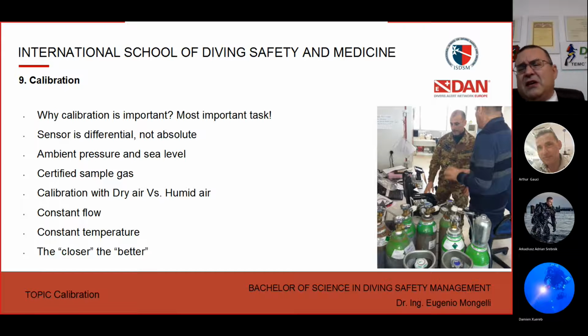Typically it's Air Liquide, Sapio, or SIAD, the typical gas suppliers, and they provide us this mix that is certified, meaning it comes with a certificate. They use a gas chromatographer, the highest possible accuracy analyzer, and they state the concentration in the certificate.